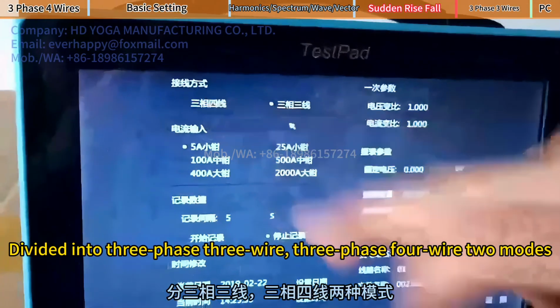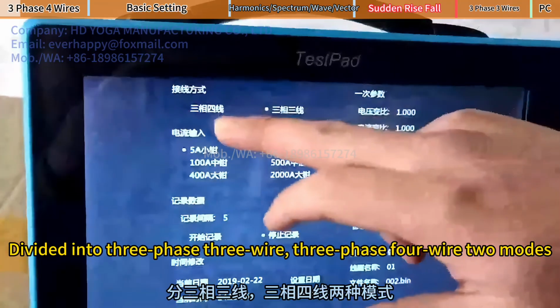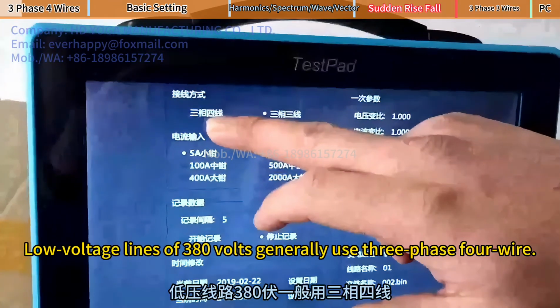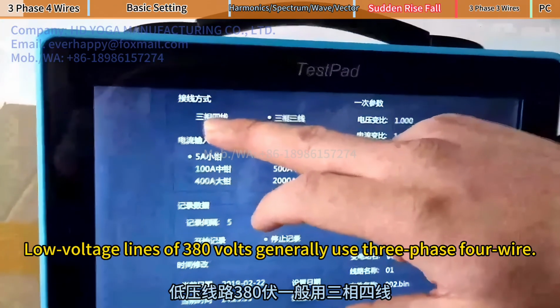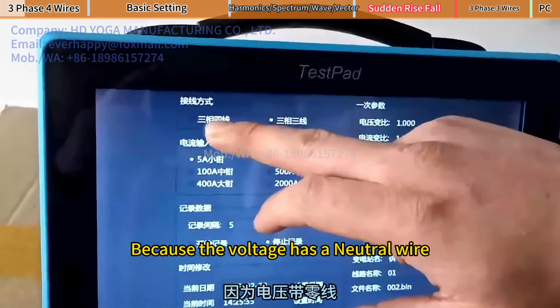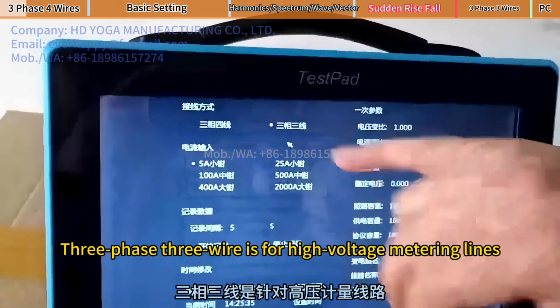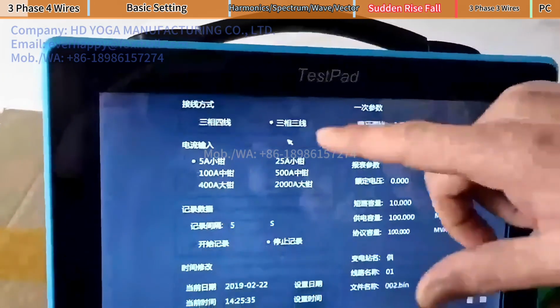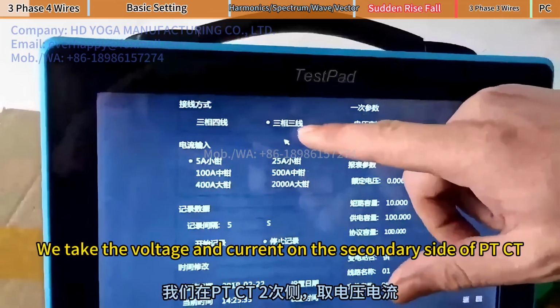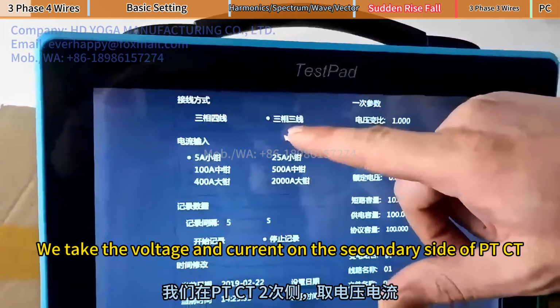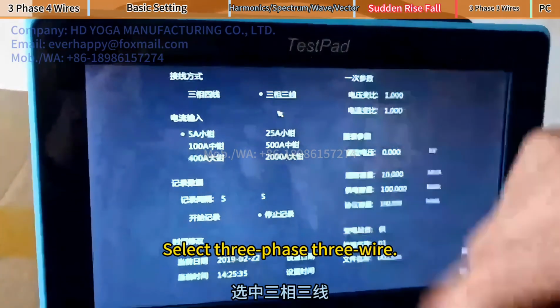Divided into 3-phase 3-wire and 3-phase 4-wire modes. Low voltage lines of 380 volts generally use 3-phase 4-wire because the voltage has a neutral wire. 3-phase 3-wire is for high voltage metering lines. It is a line via PT and CT. We take the voltage and current on the secondary side of PT and CT. Select 3-phase 3-wire. We are now in the low voltage switchgear.